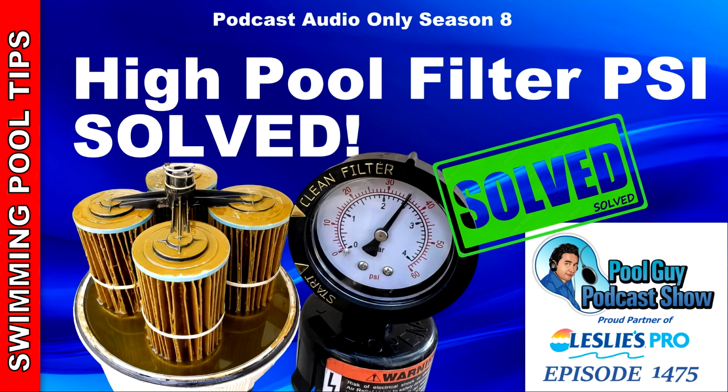So the grids on a DE filter tend to last for about 3 or 4 years, and in the old days, they used to last a very long time. I'm saying like 7-8 years without any problems, but I don't think they're manufactured with the same materials or the workmanship they used to be, so they're not going to last nearly as long. So every 3 years, you want to consider changing out all 8 grids in your DE filter.